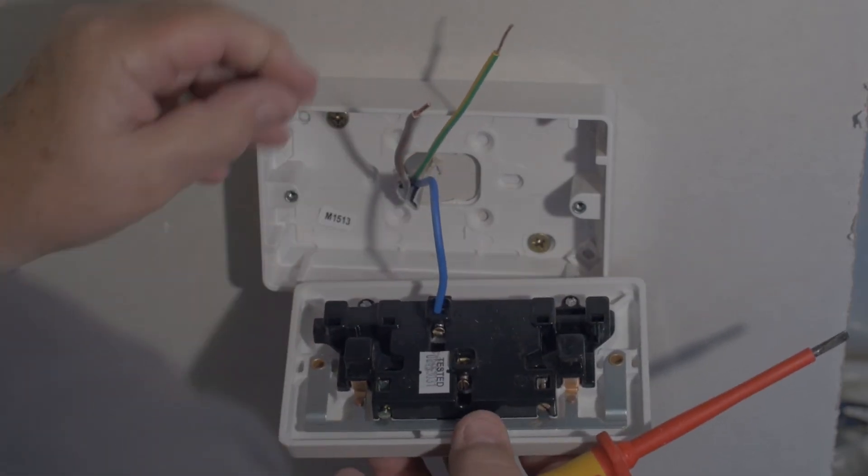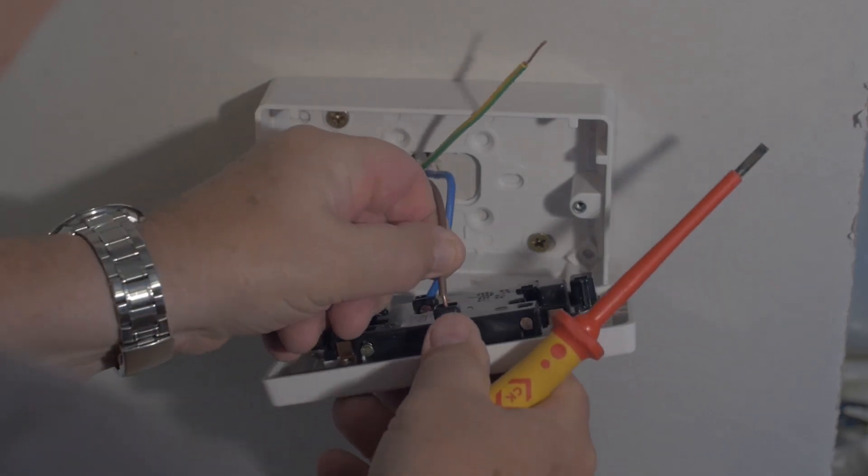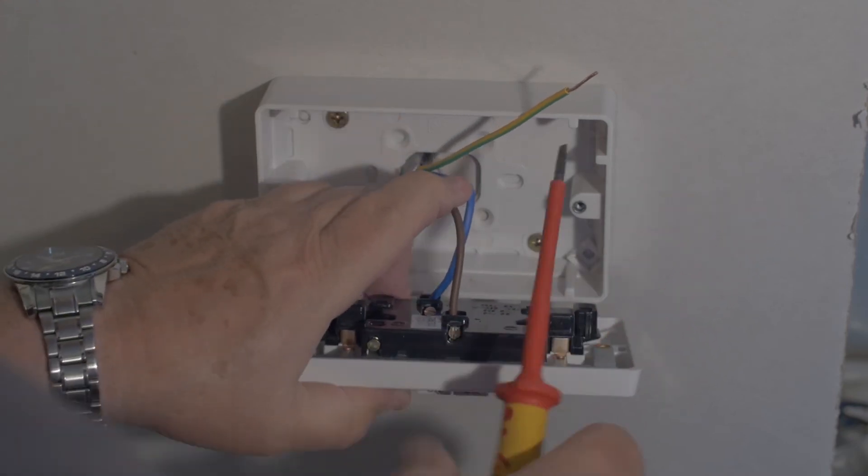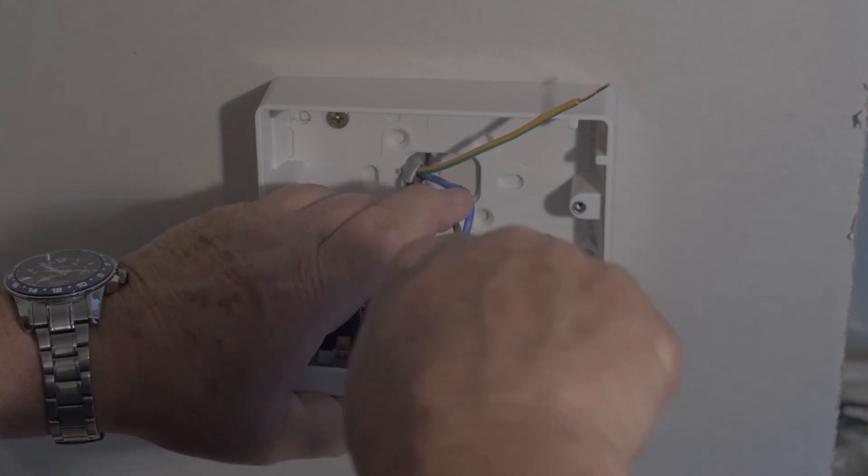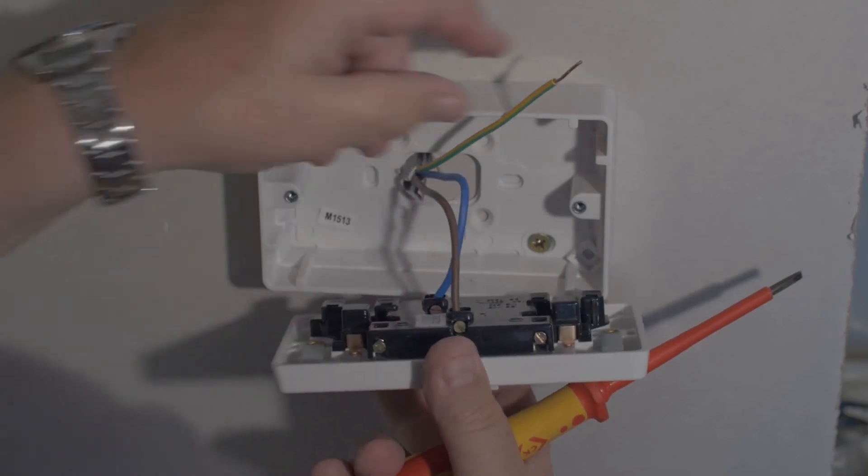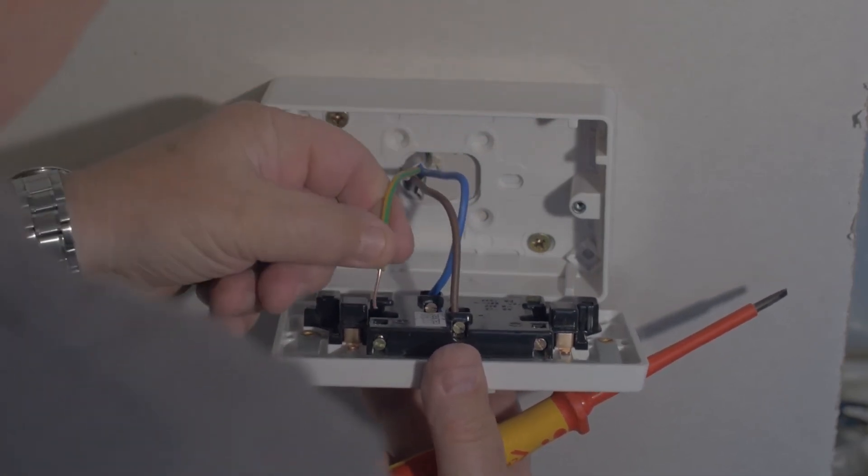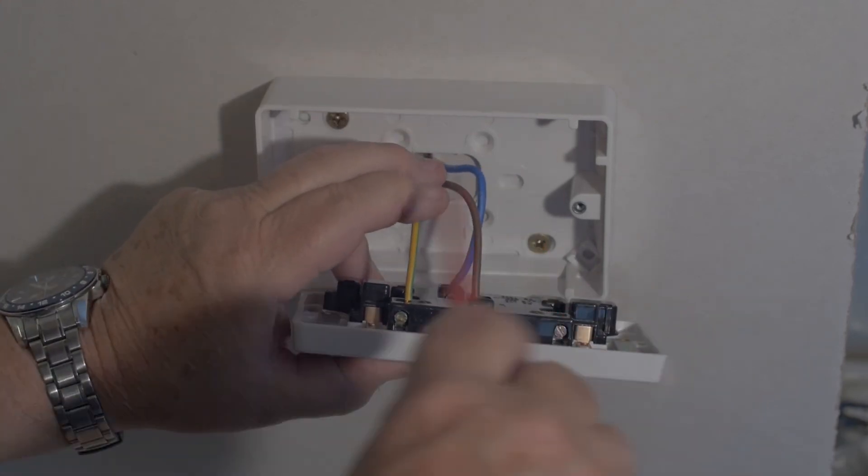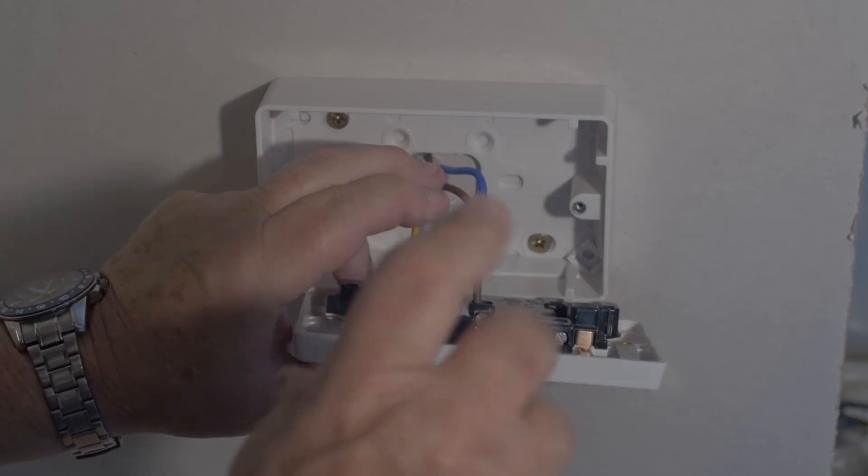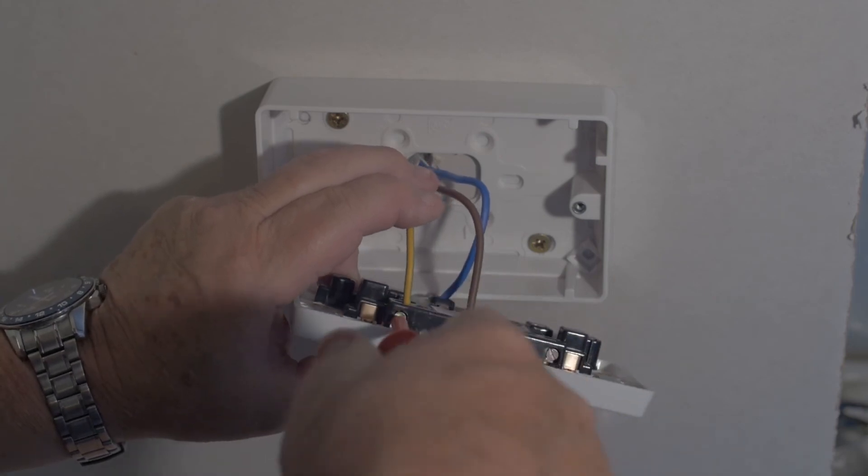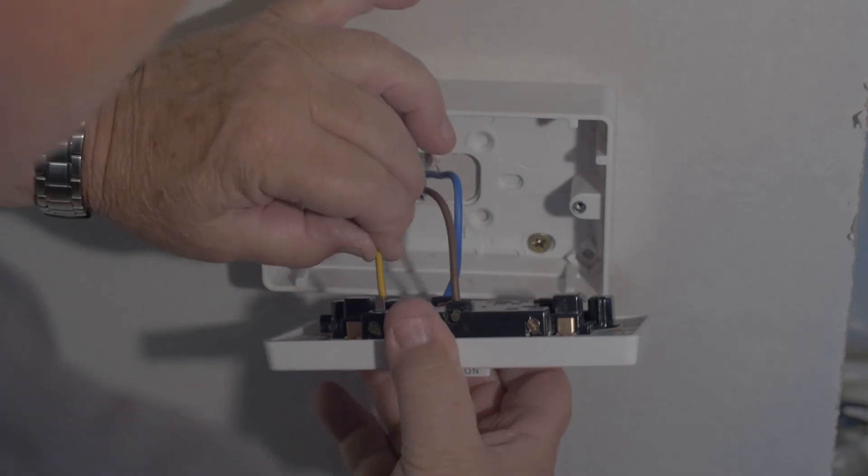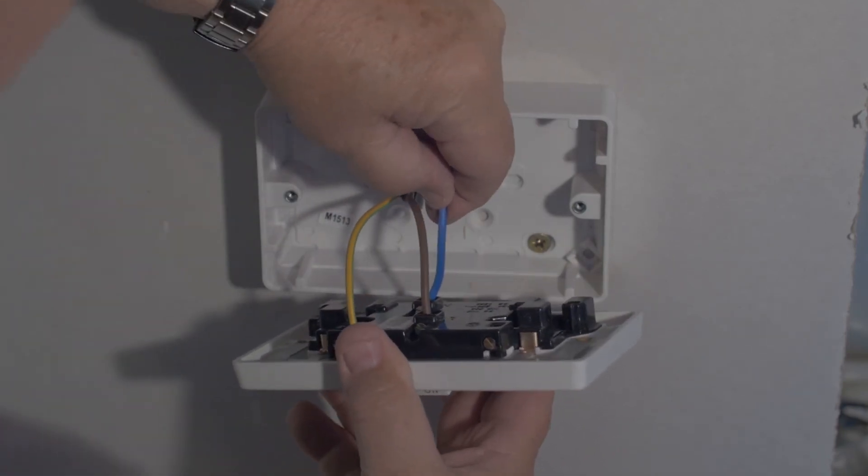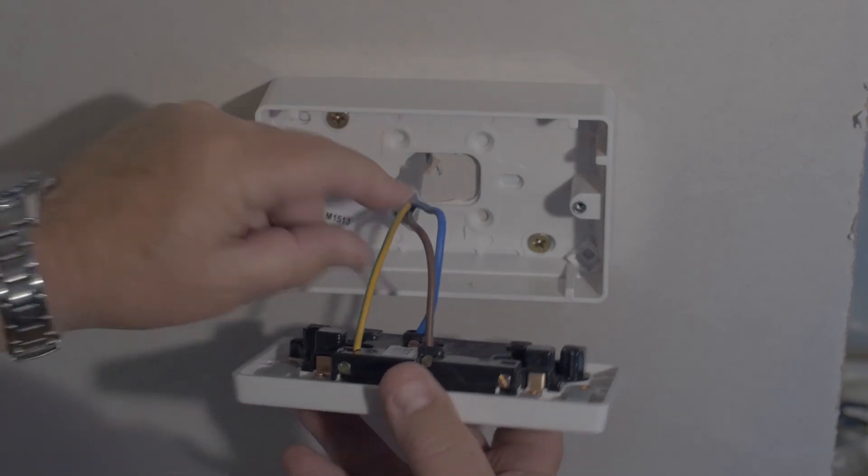Next one to do is the live. Same application. Just live into the socket and tighten down until it's snug and then one half turn. Now with the earth cable into the socket. Same procedure. Tighten down until it's snug and one half turn. Just pull each one to make sure that they're held firmly. And that's the wiring of the socket.